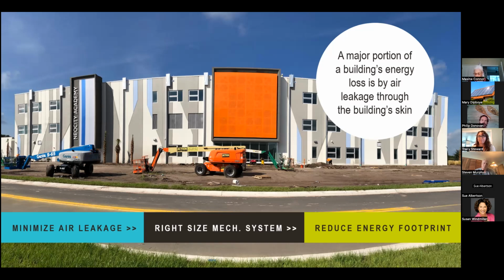Up to now, engineers design in redundancy, architects say it's going to work great, and engineers add a lot of redundancy because they don't know and don't want phone calls. Typically when we hire people, I notice the sizing of equipment on a non-tested building is 20% to 30% more capacity because of the fear of building leakage. Infiltration is a number you put in, and it gets pretty big if you have zero confidence in your envelope.